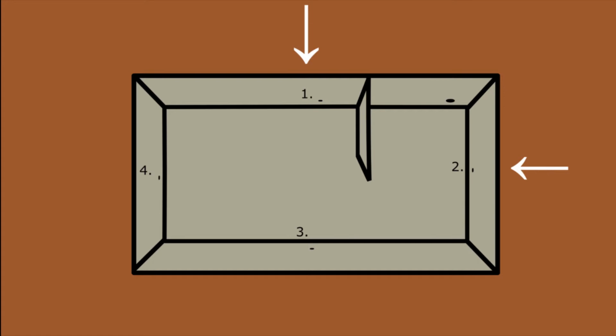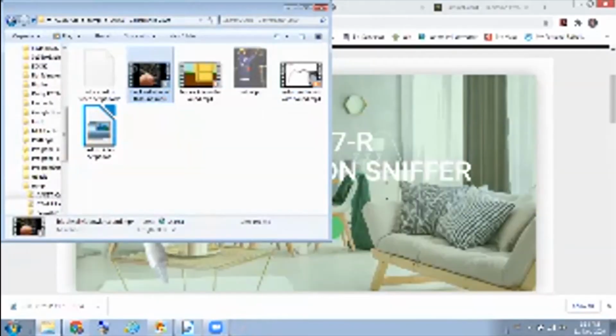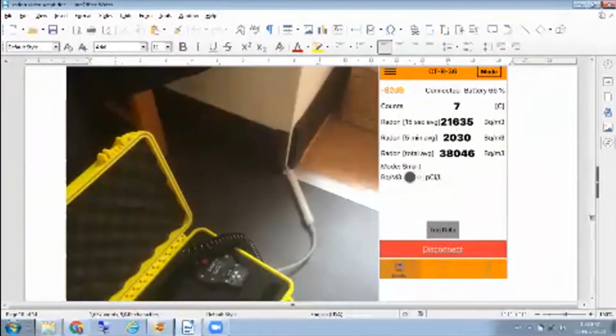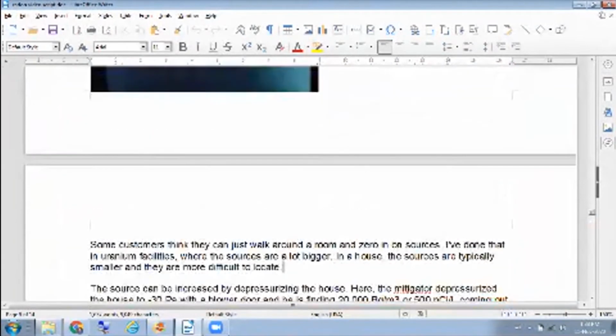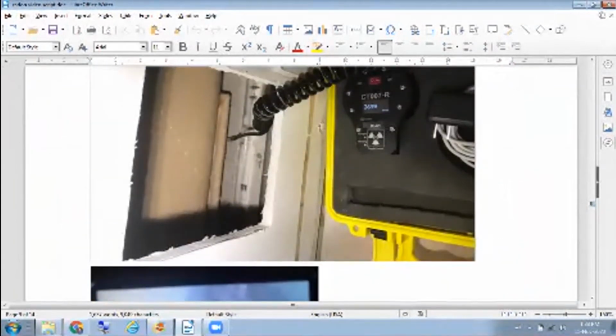He put the shop vac back where we see the larger hole in between hole 1 and 2, and was able to get a connection to both holes, meaning he didn't need to make any other further installations. Sometimes you don't necessarily want to drill holes all over the place if the place is already finished, so you don't want to necessarily do all your diagnostics like that. So some people are using the sniffer without actually drilling holes through a slab.